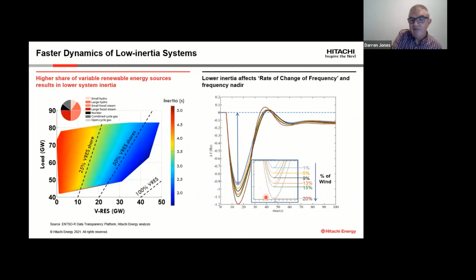What we can see here follows naturally from the previous equations that we looked at. The less inertia we have on the system, the greater the rate of change of frequency, and the greater the frequency nadir will be, which means it's more expensive or more difficult for the National Grid to then bring the system back to a stable state. So these key parameters manage and describe the system response to major events, like what I mentioned previously, the loss of a large wind farm or the loss of a significant amount of in-feed generation.